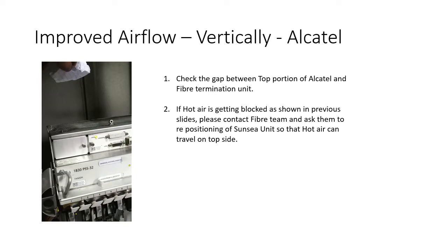In this slide, we will show you a small video clip in which you can see the improvement in the hot air discharge from the Alcatel Lucent equipment. The fiber termination unit is moved upward with the help of the fiber team, and finally the hot air discharge airflow is drastically improved and effective cooling is taking place.